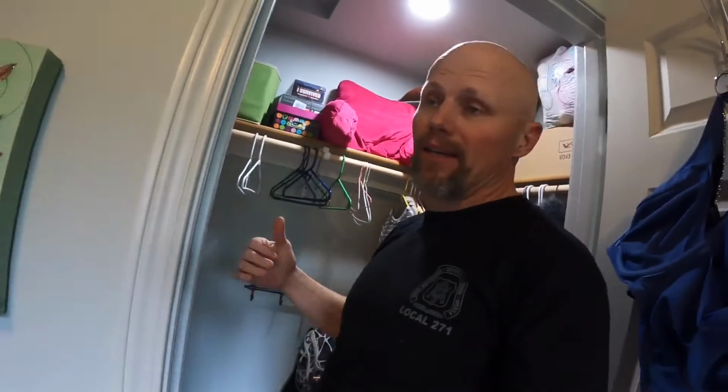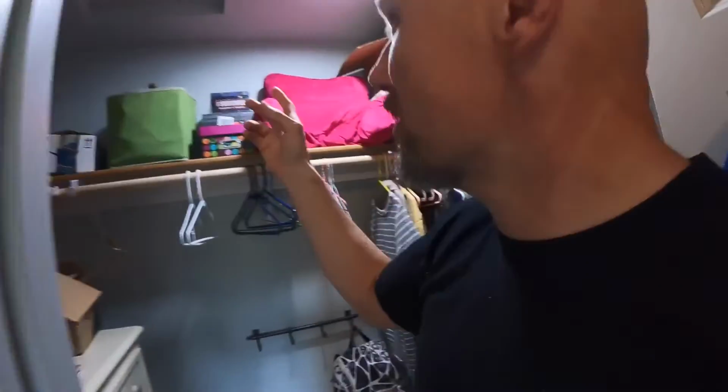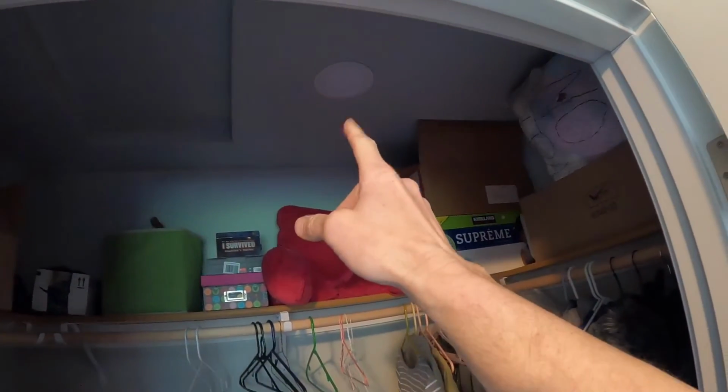So he gave me the option. He's like, hey, you can either move it, which would create another hole and that sort of thing, or put in a can light, which then gave me that clearance. I got it right around 19 inches from that back wall to the light. I did that late in the evening, got that done, so then I could call in for that inspection, because all these inspections were happening within about 5 days. That was one area that I didn't want to have to wait a week, 2 weeks for somebody to come out, fix, patch, all that sort of thing before we can call in for a final electrical. So got that taken care of. Keep an eye out for those sorts of things. You have measurements. More's better. Hey, they could have had that light fixture way over here and have been just fine.